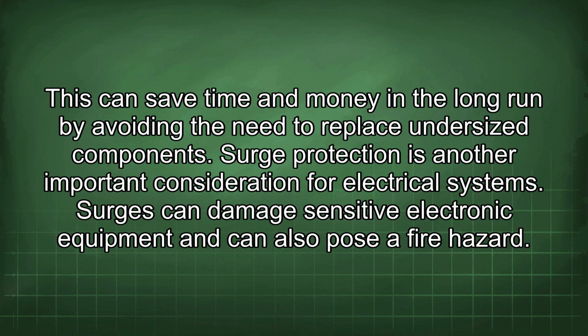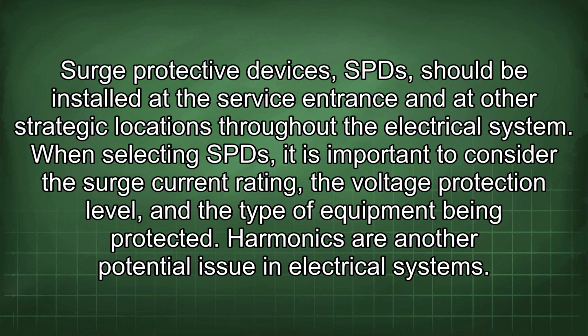Surge protection is another important consideration for electrical systems. Surges can damage sensitive electronic equipment and can also pose a fire hazard. Surge protective devices, SPDs, should be installed at the service entrance and at other strategic locations throughout the electrical system. When selecting an SPD, it is important to consider the surge current rating, the voltage protection level, and the type of equipment being protected.